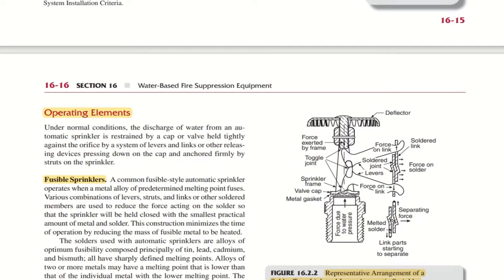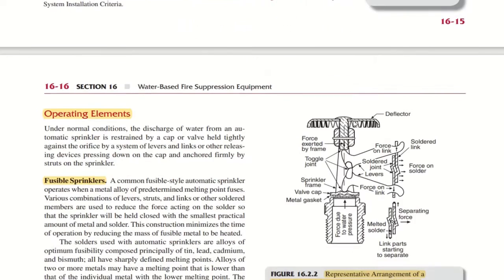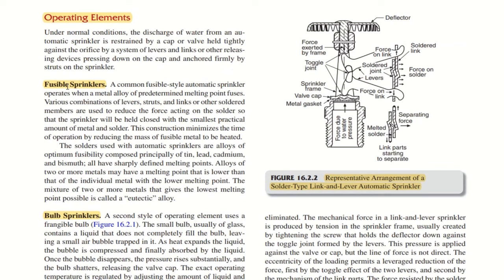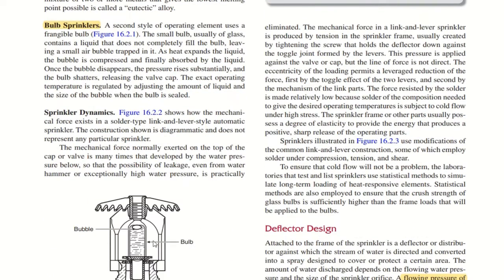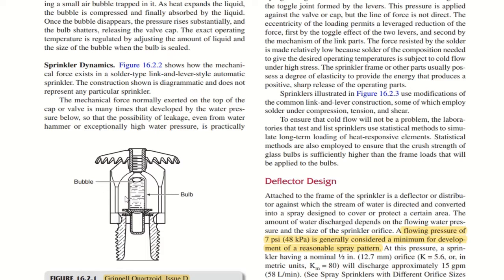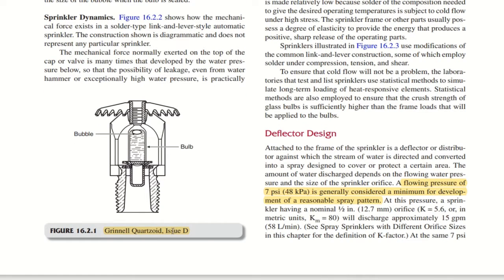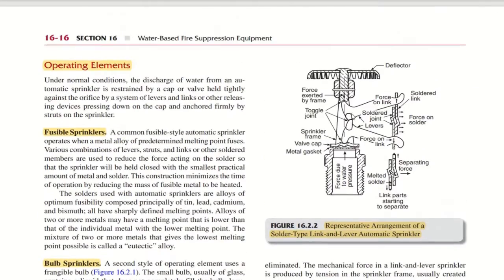In this you have some element which will burst. Once it is burst, the water will flow from the piping to the deflector, and the deflector will divert the water. Based on this deflector, the spray patterns are varied. So in operating elements you have fusible sprinklers. There will be some filaments in this particular area, or you have bulb sprinklers as well. In a bulb there will be some liquid. See the figure, Grinnell Quartzoid, they mentioned something like this, but this is a bulb sprinkler, and these are some filament type or fusible sprinklers.